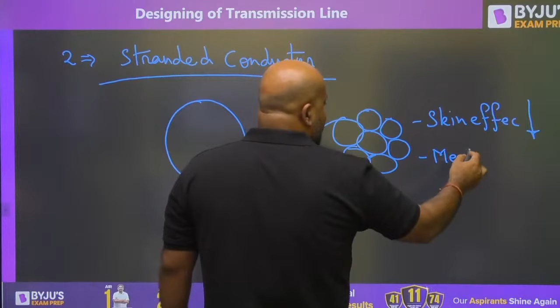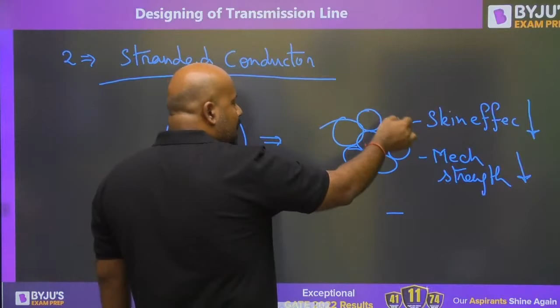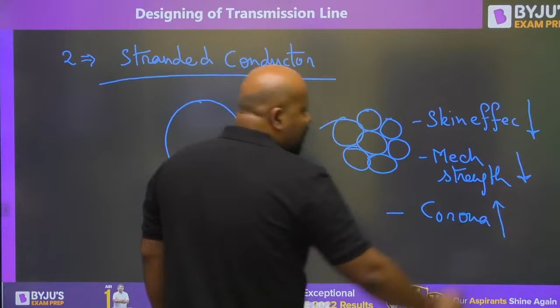Second, mechanical strength is reduced. Third, because of this irregular surface or the sharp corners, the possibility of corona or the intensity of corona is increased. It means you were going to solve some problem, but instead of solving that problem completely, you have given rise to some more problems. What are those? Number one, mechanical strength has reduced, and number two, corona is also increased.